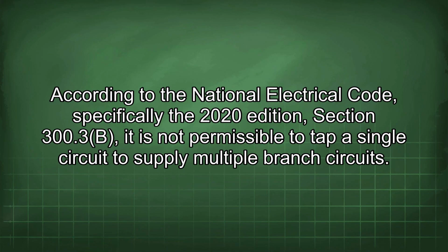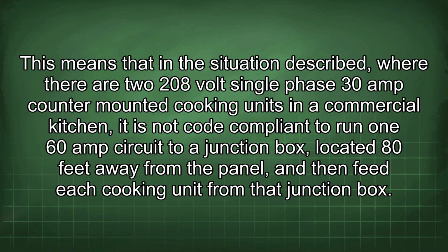According to the National Electrical Code, specifically the 2020 edition, Section 300.3(B), it is not permissible to tap a single circuit to supply multiple branch circuits. This means that in the situation described, where there are two 208-volt single-phase 30-amp counter-mounted cooking units in a commercial kitchen, it is not code compliant to run one 60-amp circuit to a junction box located 80 feet away from the panel and then feed each cooking unit from the junction box.